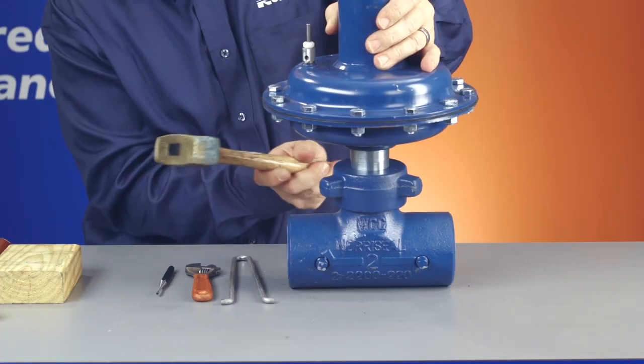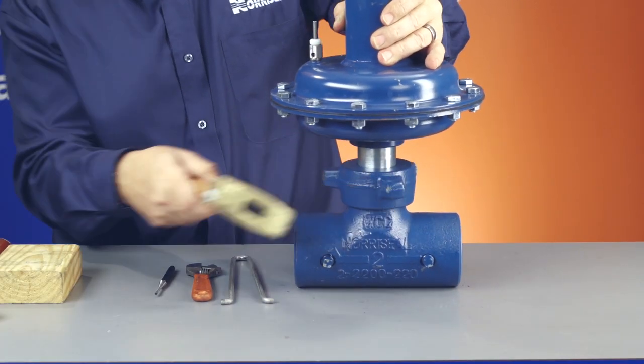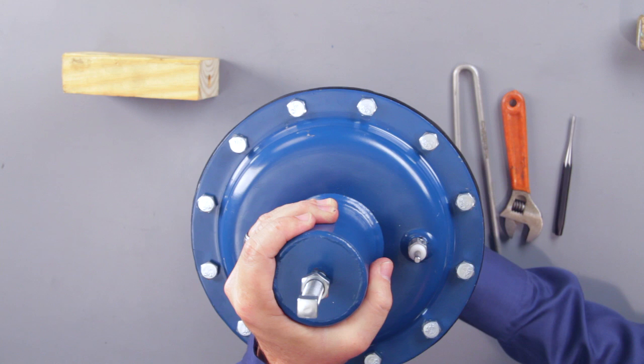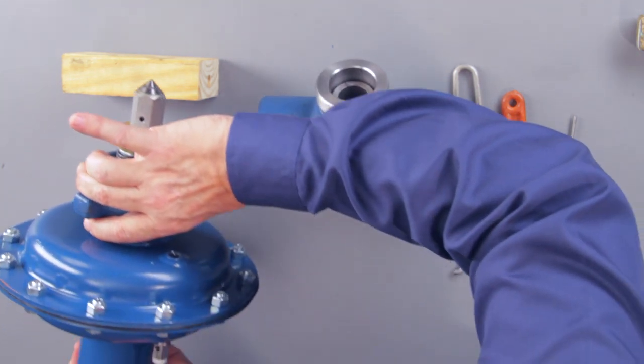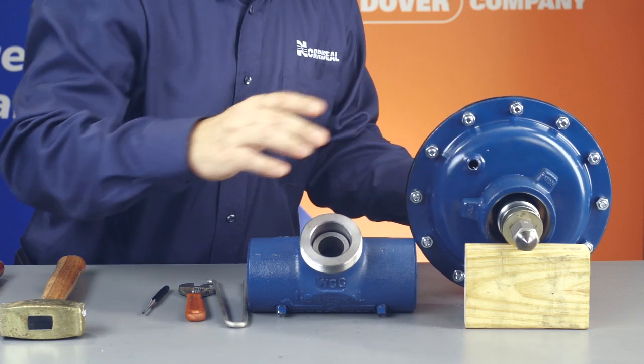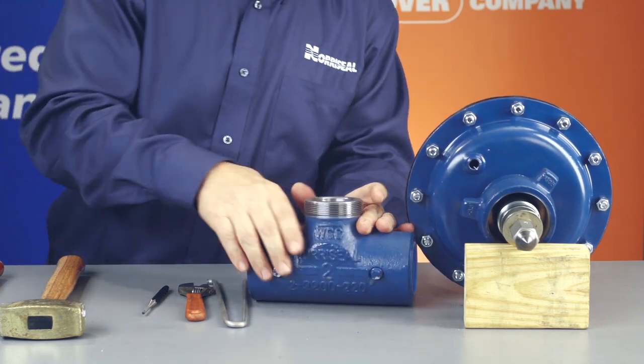Next, unscrew the hammer nut from the valve body by striking the lugs with a hammer. Then, lift the actuator from the valve body and place it on a stable work surface. Make sure you don't damage the o-ring sealing surfaces when you remove the actuator from the valve body.